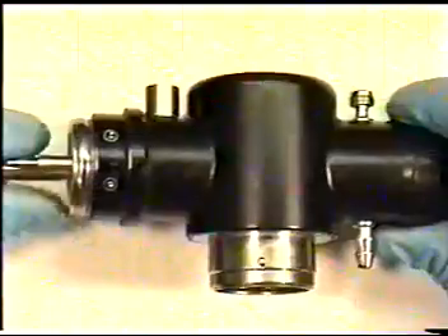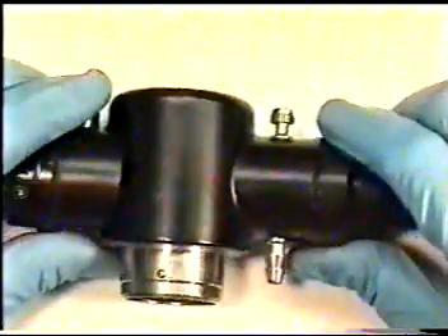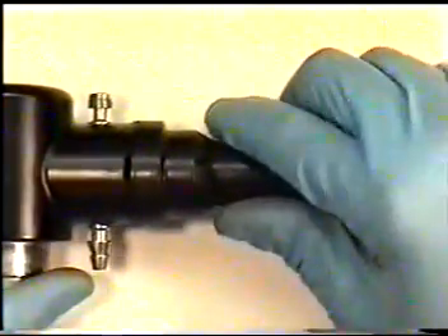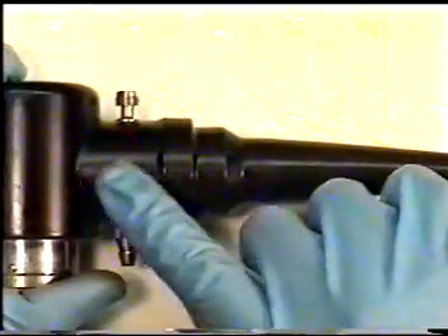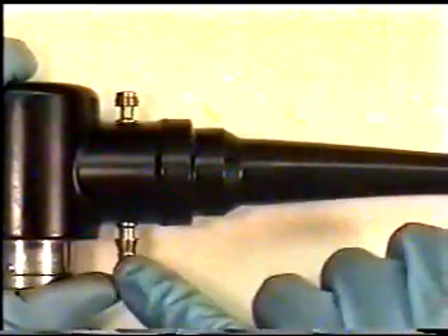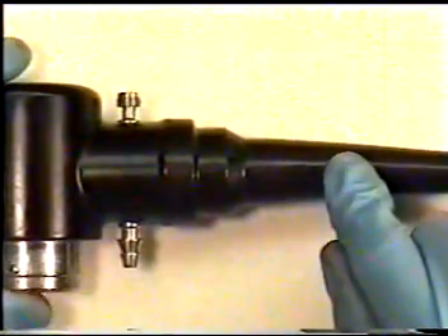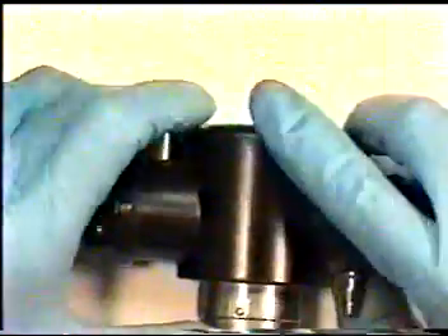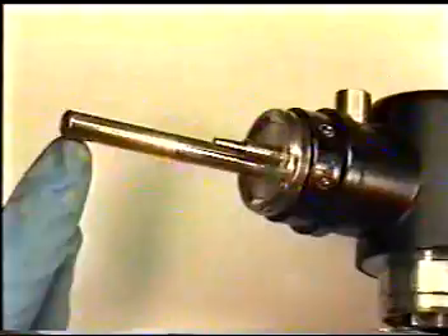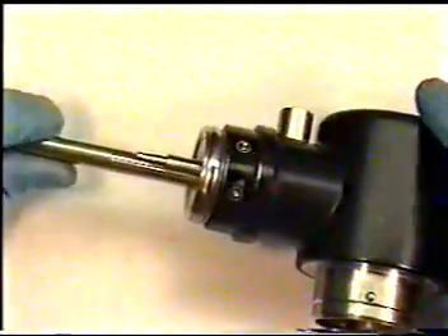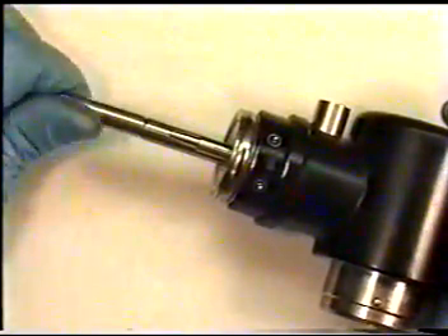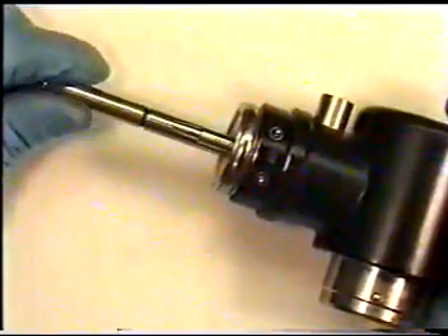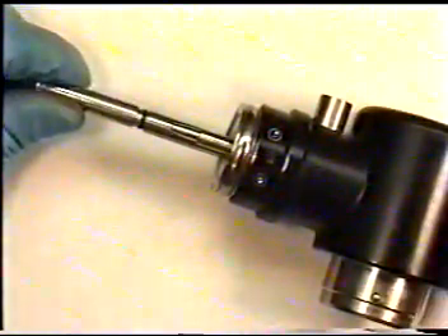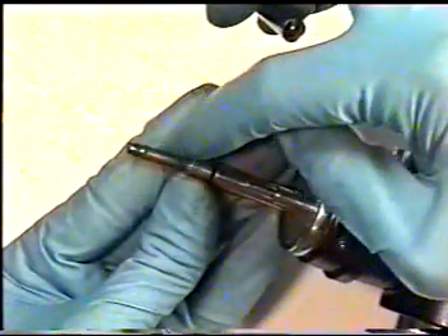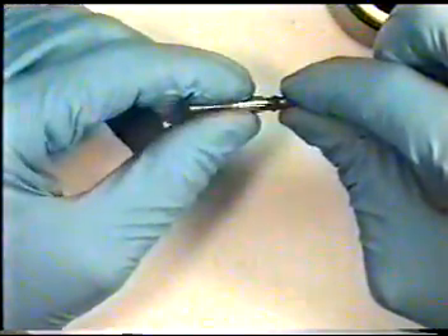Moving down to light guide probe connector assembly. You'll need to remove the cone from your light guide connector assembly in order to gain access to our suction channel and our light guides, which run through the umbilical control section, through our connector, and to the light guide probe end. First step is to unscrew a light guide probe sleeve counterclockwise. Remove the sleeve completely to expose our old damaged light guide proximal fitting. Remove light guide proximal sleeve.